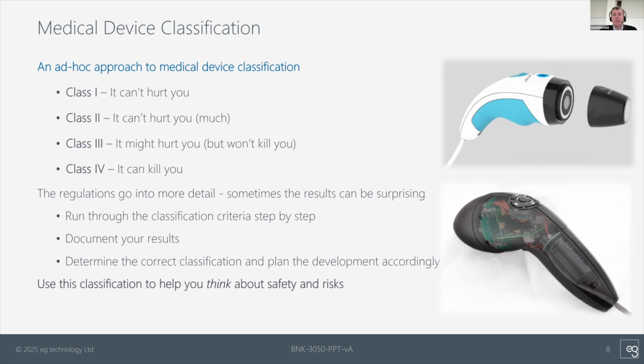It's also worth noting, though, that if you take that class 1 device at the top of the screen, if you were to, for example, add some machine learning to that device that automatically reviews the images, perhaps makes a determination as to whether to refer the patient for a follow-up, then that top device falls under what is Rule 11 in the MDR, dictating that software that helps to guide clinical decisions is also a Class 2A device. So there's been no change in physical hardware, but your intended use has shifted and the claims you're making for your product have shifted to the point where you're providing diagnostic support and a higher degree of regulatory scrutiny is applied. So with that in mind, the point here is that device classification should help you think about your overall device safety and acceptable levels of risk.